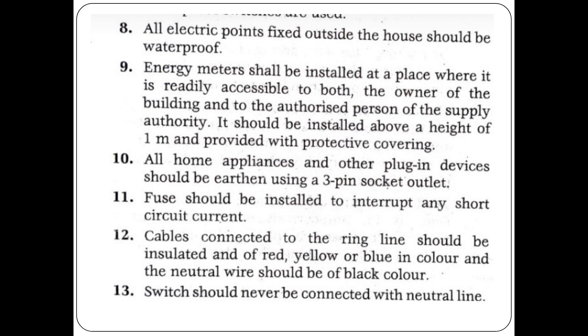The energy meter shall be installed at a place where it is readily accessible to both the owner of the building and the authorized person of the supply authority. It should be installed above a height of 1 meter and provided with a protective covering.